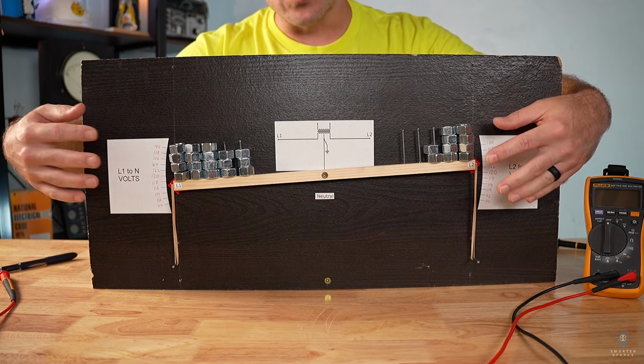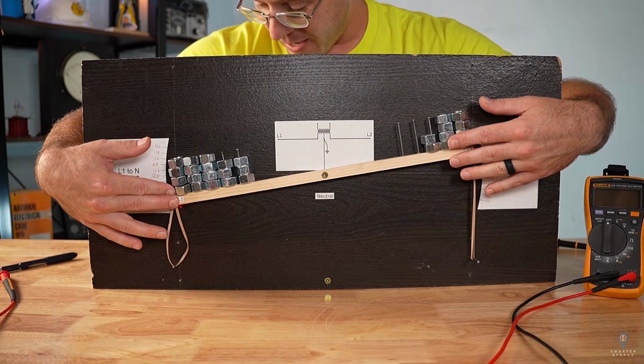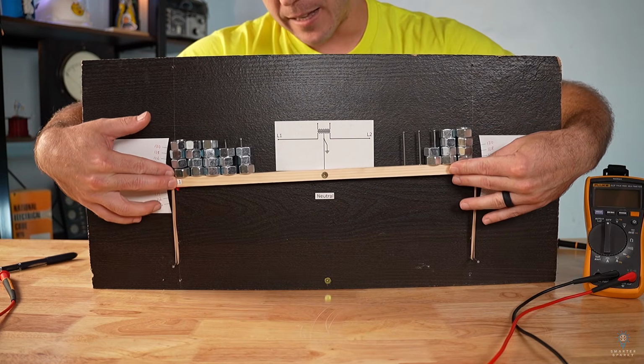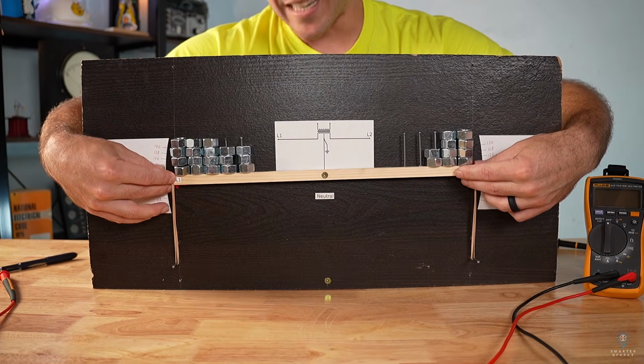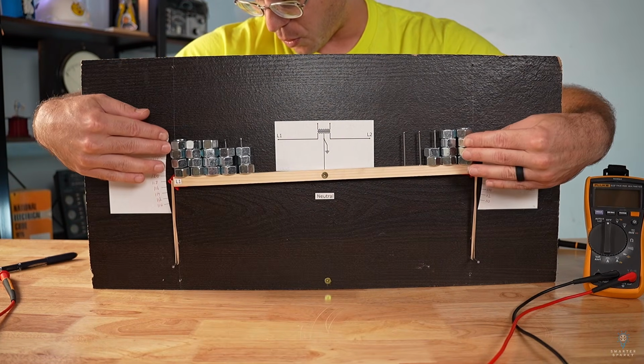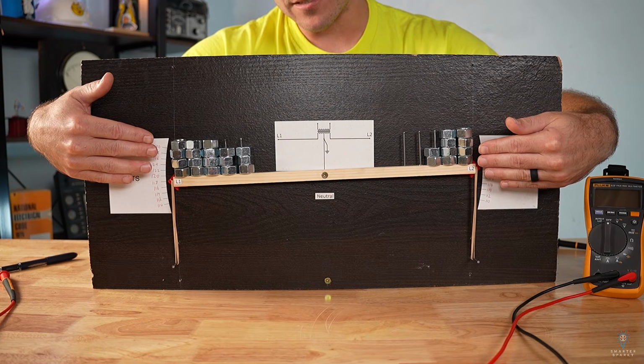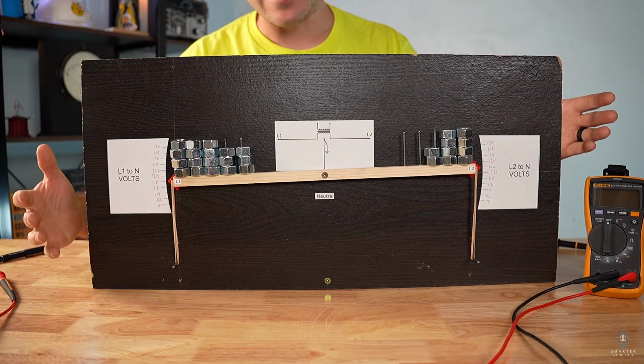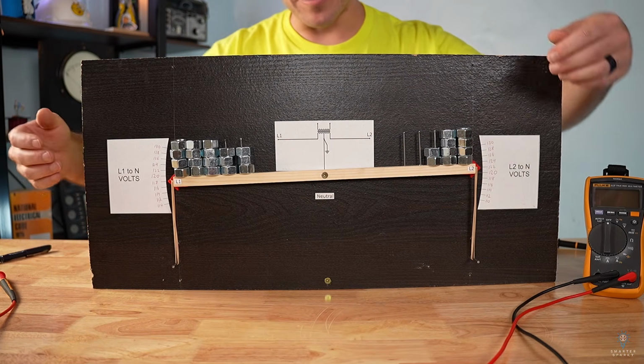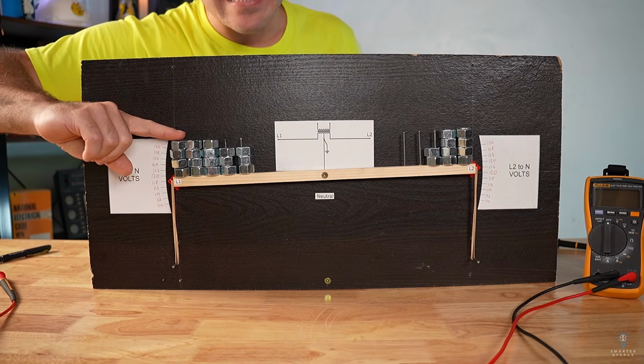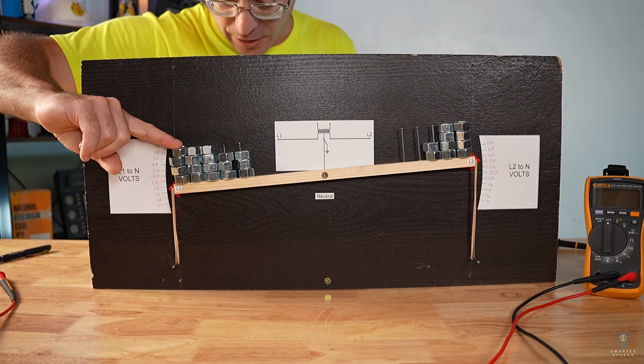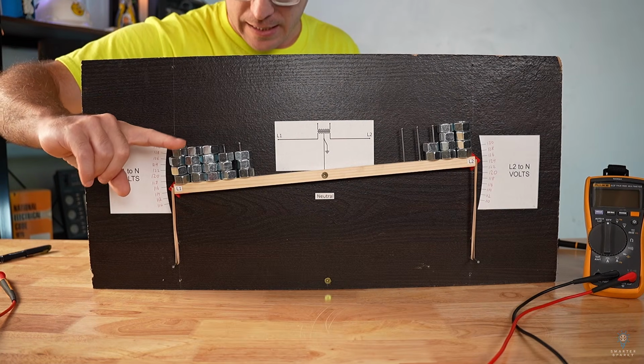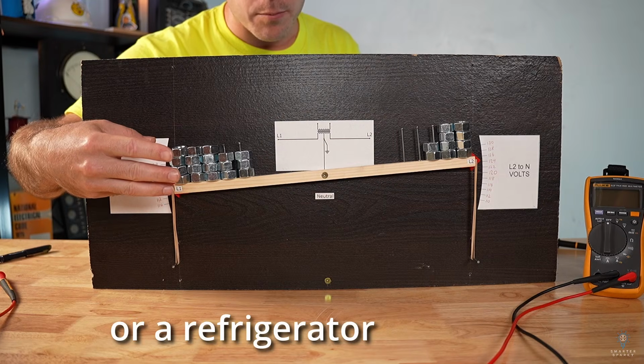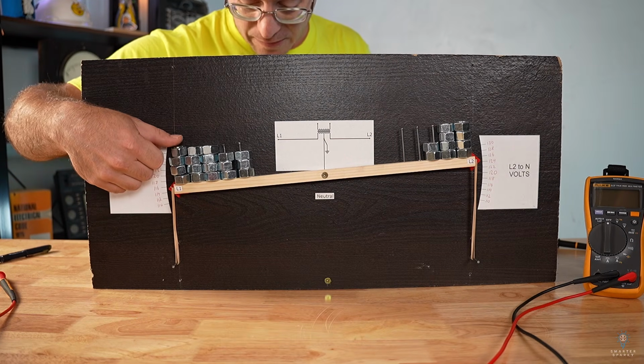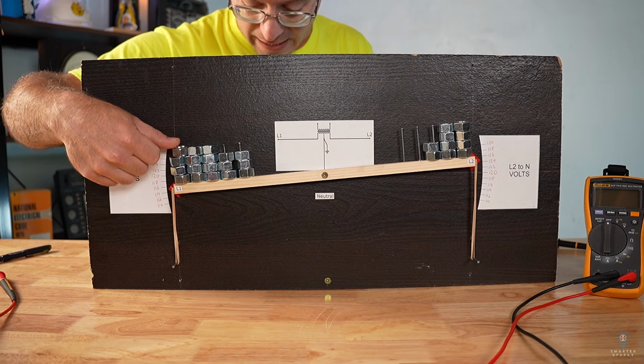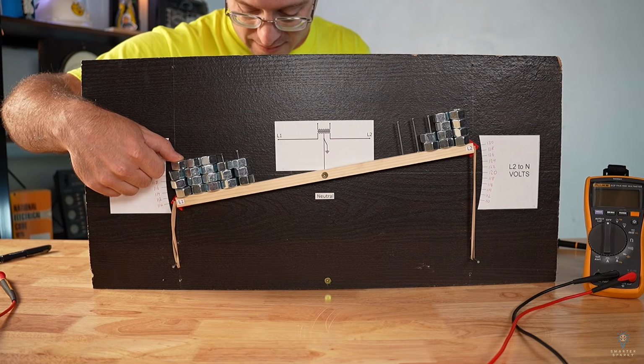So we can think of a loose neutral as this beam that is trying to balance, but the center point is so loose it can't hold that extra weight if things are imbalanced. Furthermore, motors have a massive inrush current on startup, and what that does is it adds an even heavier weight for a fraction of a second while a sump pump is kicking in, or an air conditioner, or a dehumidifier. So when those motors kick on, there's a huge inrush current on that line, and that further imbalances the voltage.